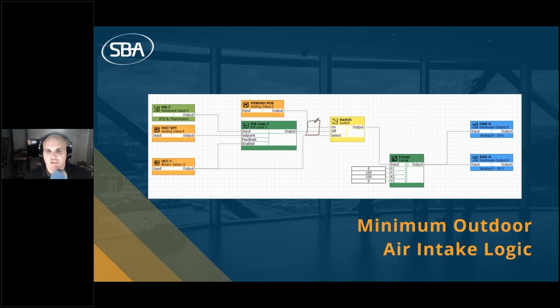So the minimum position would go into a max block. The PID loop would go into the max block. It would take the higher of the two, and then it would take that when it's occupied. And when it's not occupied, it would take an actual off value, a 0 value. Still goes into the linear comparator and then drives these right there. All right, so that is how you would do basic mixed air temp with a minimum outdoor air damper position that is set by the balancer.